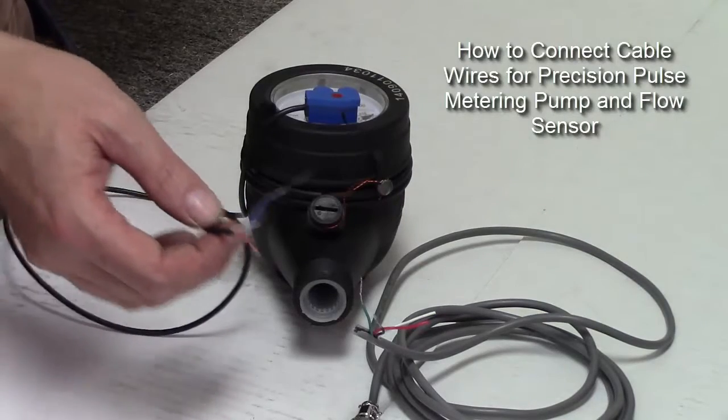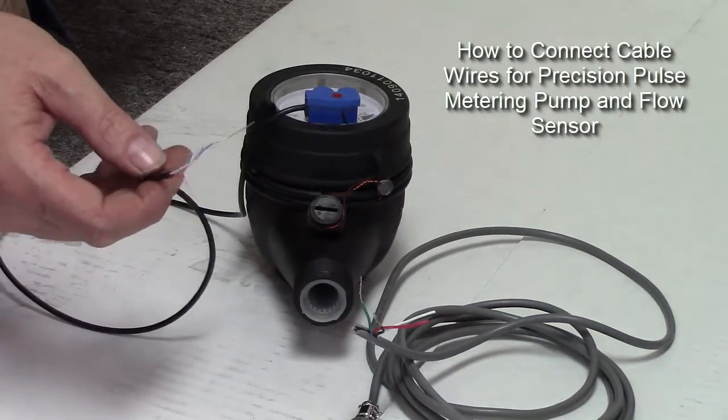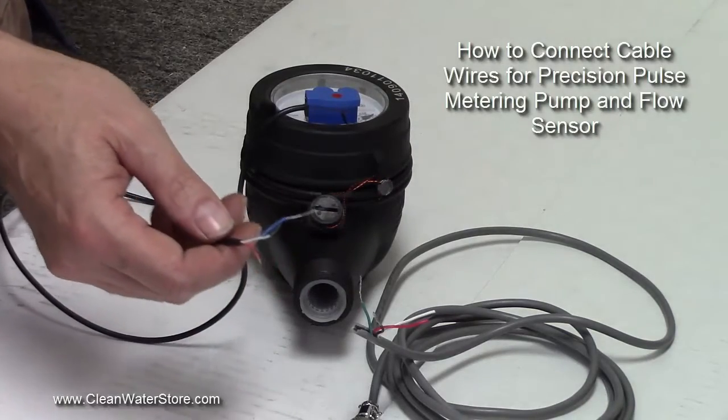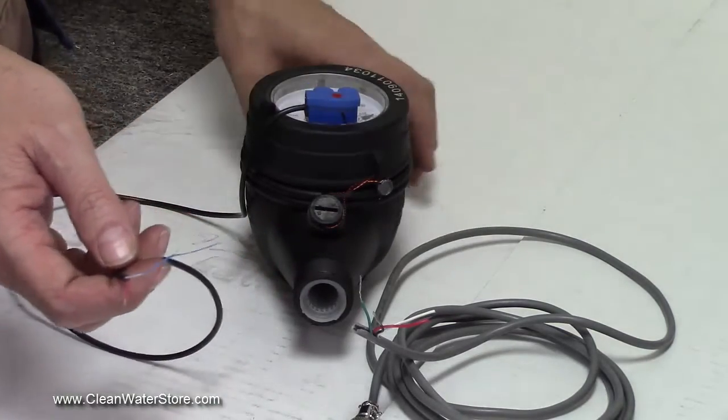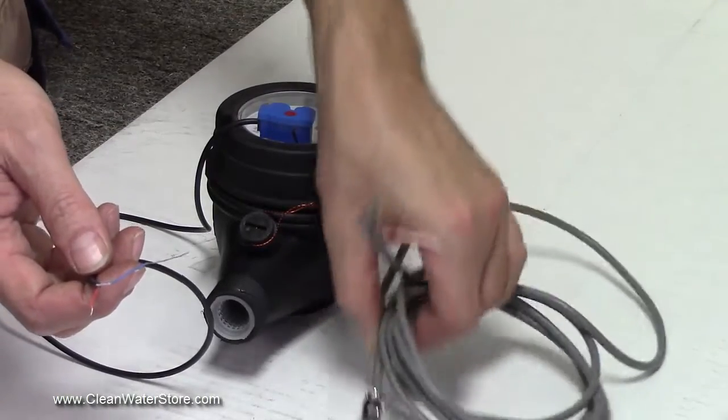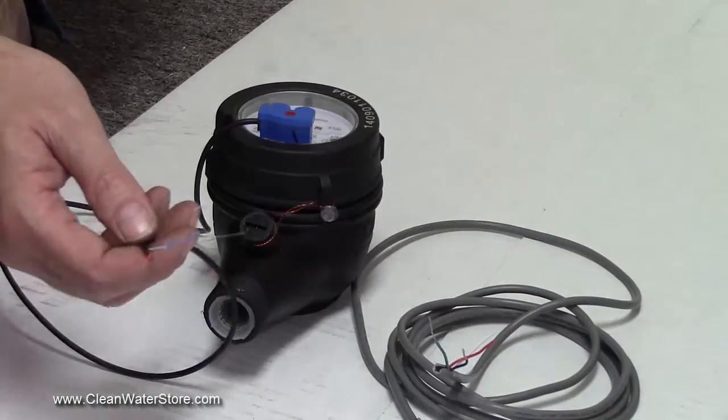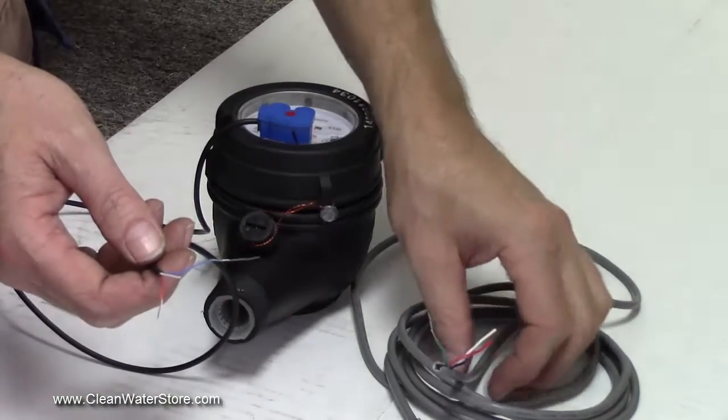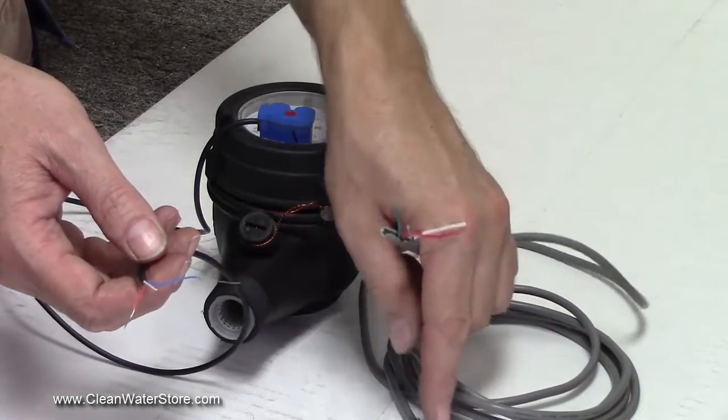Howdy folks, short Clean Water System instructional video on the color coding of the wires to hook your flow sensor up to the cable that goes to the Precision 24 unit. The Precision 24 cable has four connectors and thus it has four individual wires which are green, black, white, and red.